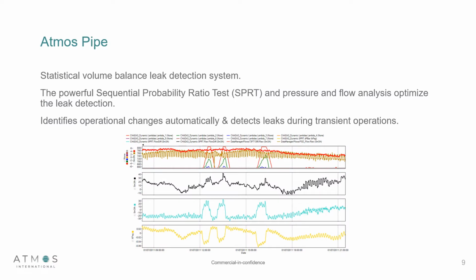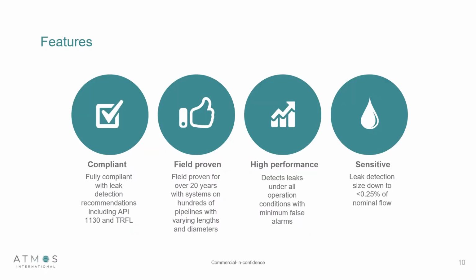Atmos Pipe is a statistical volume balanced leak detection system, and it was primarily developed as a software-based LDS. It would utilize SCADA data and existing instrumentation on the pipeline to provide a reliable flow and pressure analysis. It can identify operational changes automatically and detect leaks during transient, dynamic and static conditions. It is fully compliant with the API 1130 and TRFL.